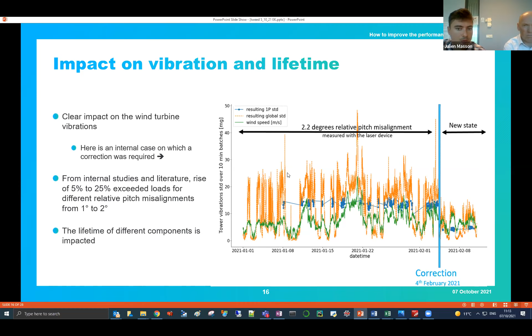And there is an impact on vibration and so lifetime. Here you can see the high decrease of the vibration level. This is the same case as I showed before, same turbine. Here we show the period just before and after the good correction, so the second correction by the OEM. It was a 2.2 relative pitch misalignment. You see orange and blue, 2 vibration indicators, and both decrease right after. And in green, you have the wind level in meters per second. So you can see that there is a straight link between pitch and vibration, pitch misalignment especially. And that's what we will use to detect it. But I'll let Elmar continue with the yaw.